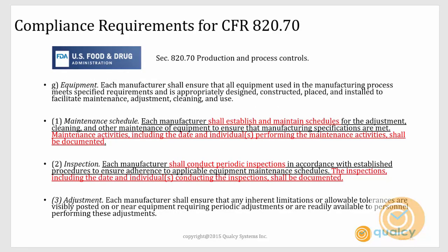So these are some of the compliance requirements as outlined in CFR 820.70. This is the medical device QSR regulation. As we mentioned briefly in the previous slides, the manufacturers shall establish and maintain schedules for the adjustments, schedules for the PMs, and schedule for the calibrations.